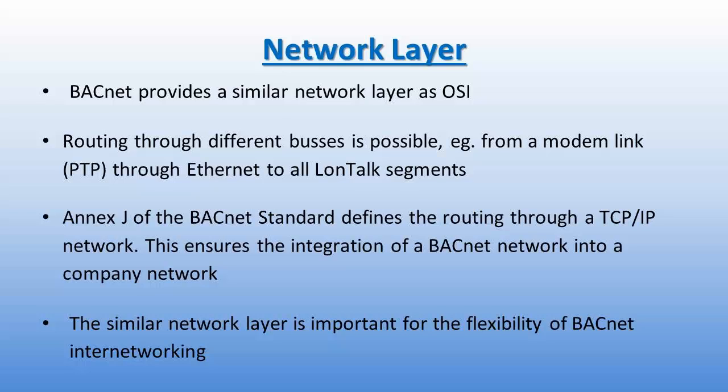The BACnet network layer and the OSI network layer are very similar, though some functions assigned to the network layer in the OSI model are not required in BACnet. One example is selecting a communication path between source and destination devices. BACnet imposes a requirement that at most one active path can exist between two devices. BACnet defines network layer protocol services that allow router tables to be configured, allowing routers to search for the path to a destination network and manage temporary connections to remote networks through a dial-up telephone connection. Routers can also indicate to client devices that a path to a destination cannot be located.